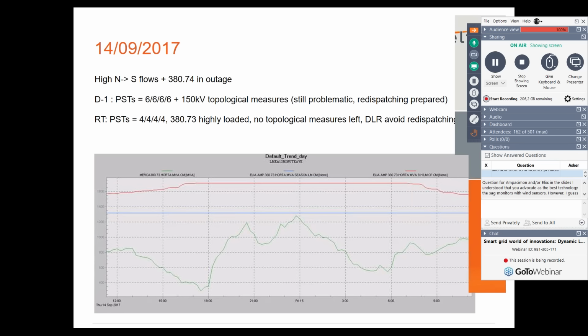So that was today, a typical day in the Belgian network. We had international flows going from the Netherlands towards France, and this was loading some lines on the way around, internal lines. We had to adapt the PST, the phase shifting transformer. We had 4 of them at the border, and we had to reduce the taps to a 6 position. 6 position is already really low because neutral position is 18 and lowest position is 1. So in day ahead, we had already to go to this situation for the 4 PSTs, 6, 6, 6, 6.